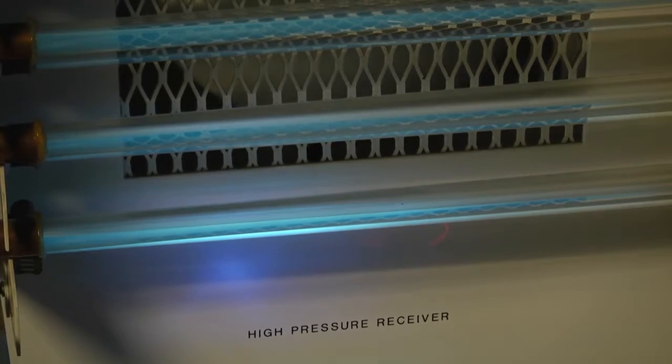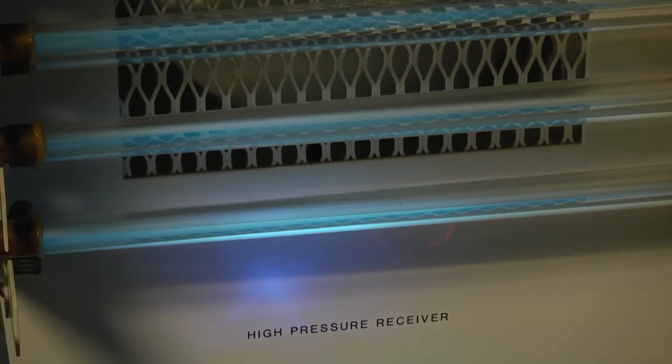It's really not an effective method of heat transfer. The most effective way to transfer heat is by changing the state of the refrigerant. However, by subcooling it, we are guaranteeing that the liquid refrigerant that travels back to the metering device to start this process all over again is 100% liquid refrigerant below its condensing point.